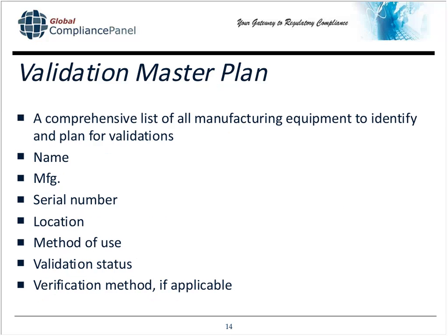A validation master plan is a great document. It's an aid that helps you determine which equipment requires validation. In truth, it's really nothing but a big list. And on this list, a spreadsheet, let's say, or a database, you have name of the equipment, its manufacturer, its serial number, its location. Now, location is temporary at some point, but you have its location as far as what's officially logged in the records, how it's used, and its validation status.